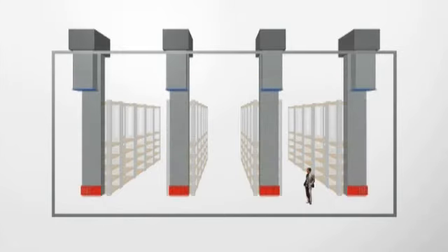So we are no longer going to draw in warm air from the ceiling. We're going to draw in cooler air much closer to ground level. And we're going to allow the building from a height of 7 or 8 feet all the way up to 24 feet to become warm. We do not need to air condition this air unless your products arrive in refrigerated trucks. They don't. What does it matter what temperature it is on the very top shelf at 18 feet within your store?